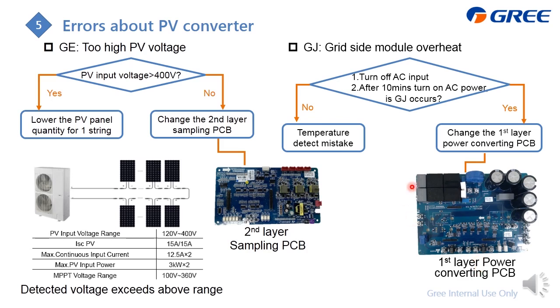So on site, what you need to do is just turn off the PV input and the AC input, and after 10 minutes turn on the AC power again to check whether this GJ error occurs again. If not, that means there is something wrong or a misjudgment from the built-in temperature sensor. And if it still occurs, that means something is wrong with this PCB, the detecting circuit, so you need to change this first layer converting PCB.